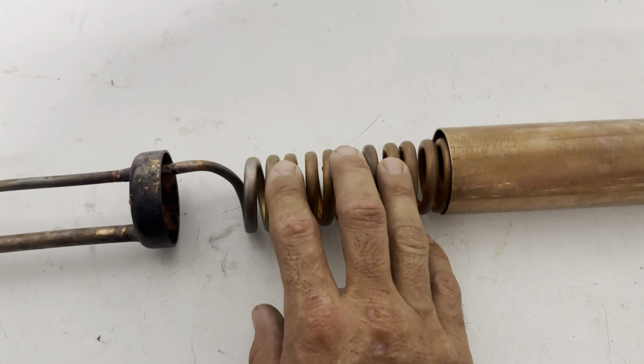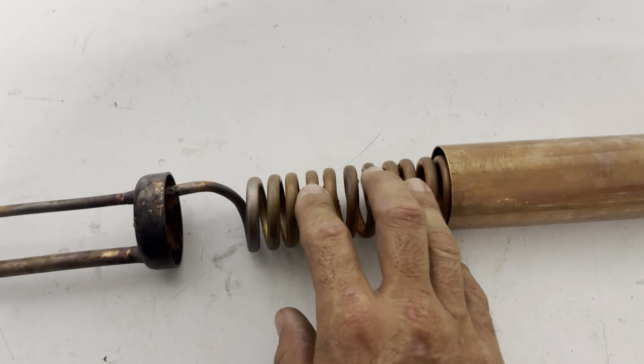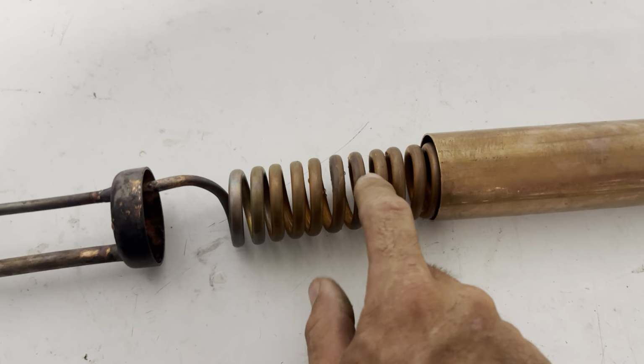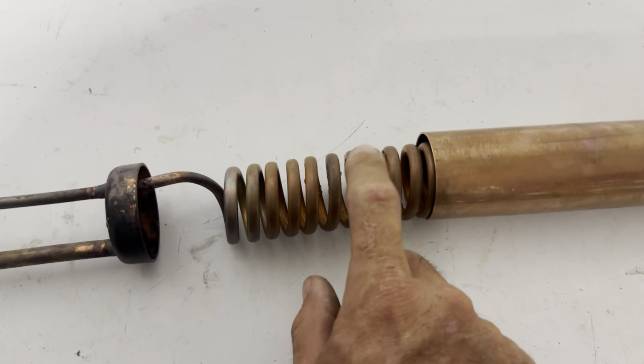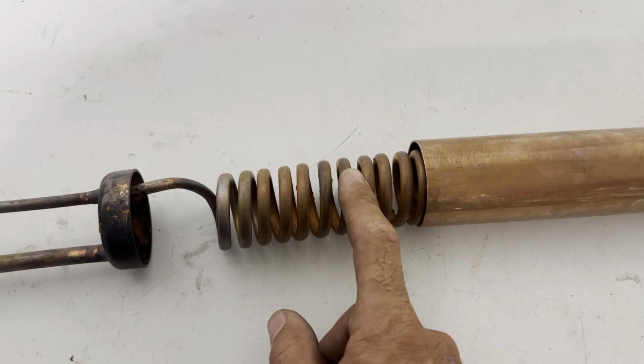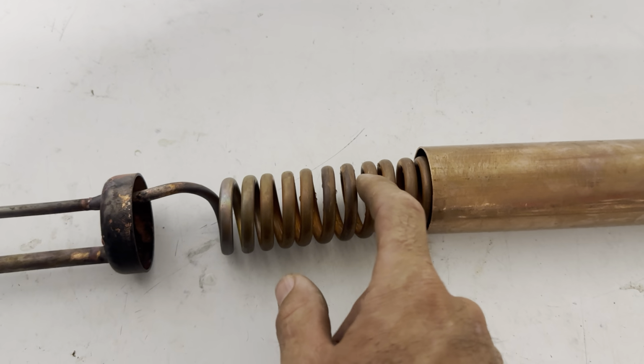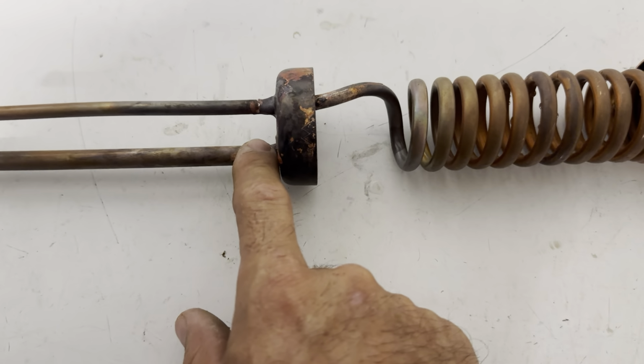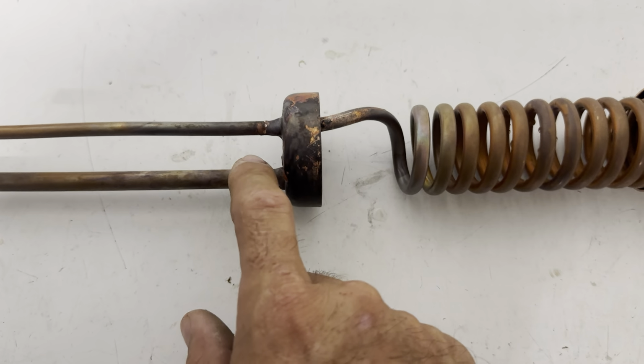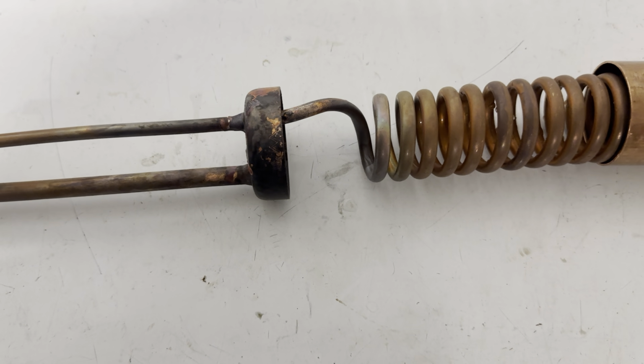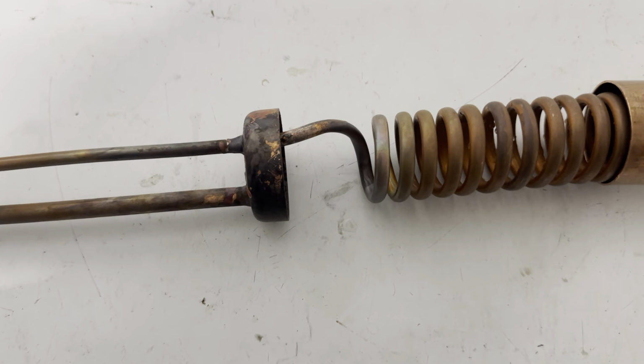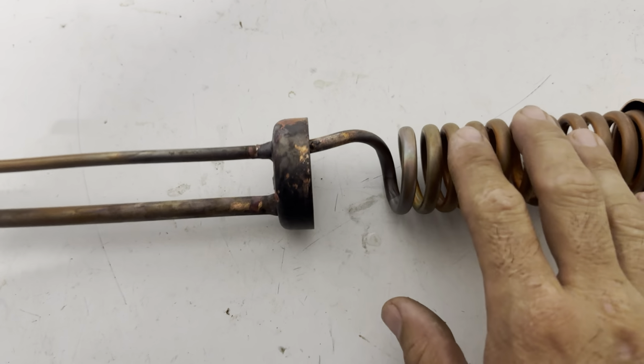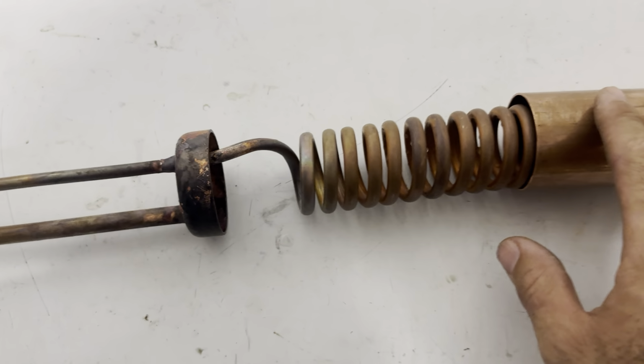So you're putting cold temperature back into the liquid line, which gives it a bit better performance. It also pulls heat out of this and puts it into the suction line, which minimizes liquid in the return, so it basically minimizes any chance of liquid hitting the compressor or liquid slugging in any way. It doesn't stop it, but will minimize it.